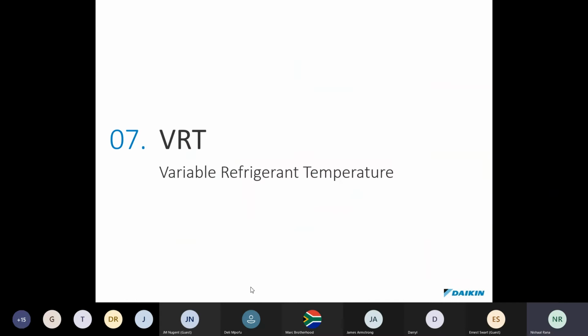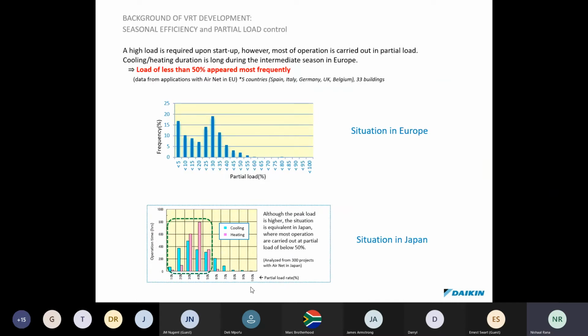We've had VRT on our VRV IV also. VRT is your variable refrigerant temperature. Let's say, for example, a high load is required on startup, and most of the operation time is on part load. What I mean is that at 8 o'clock in the morning, your office opens and everybody walks into work. The aircon is doing its maximum duty, because it's trying to cool down, number one, the structure, and number two, to remove the heat of the people load that has entered the building.